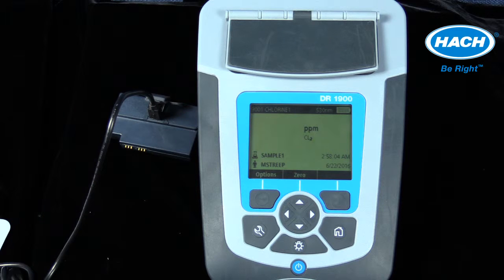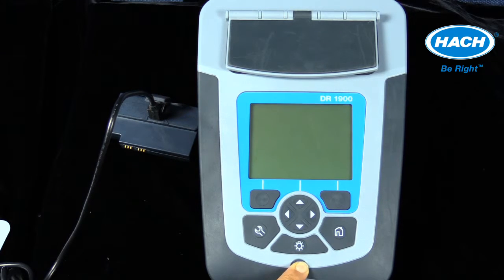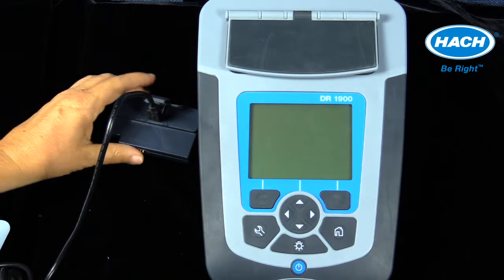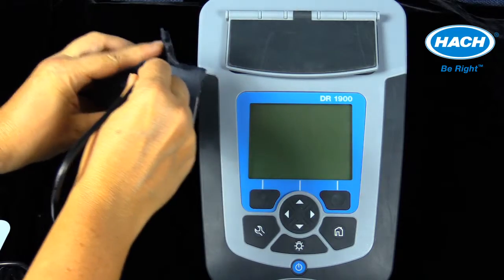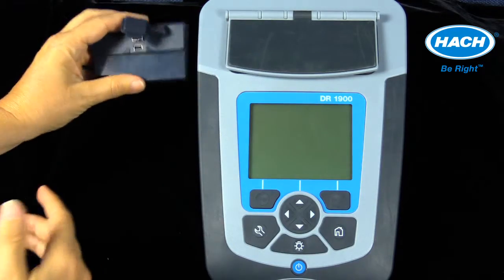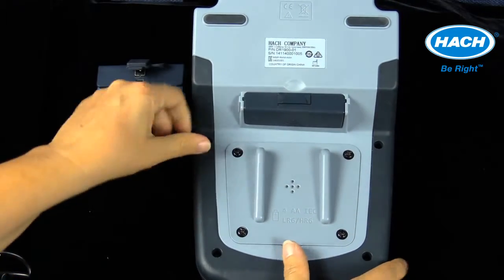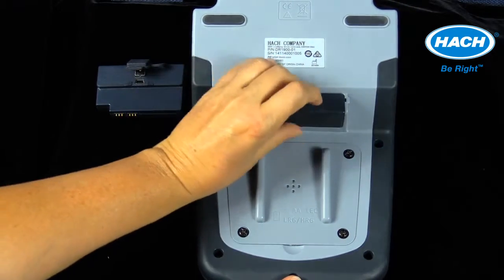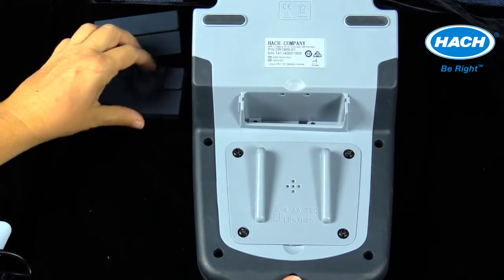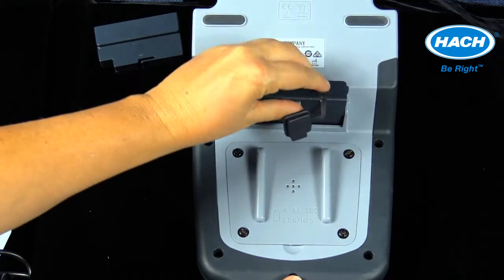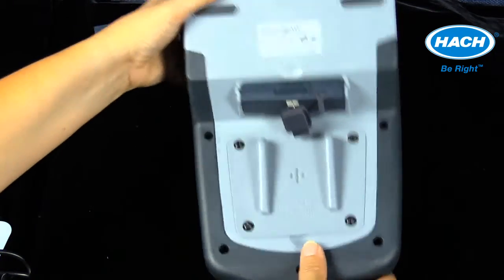The USB module, acting like a USB flash drive, can now be transported to the location of the DR1900 to complete the software update. Power off the DR1900 and remove the module blank by pushing down on the tab and pulling the module straight up from the instrument. To install the USB module, first remove the protective cover from the module and slide into the DR1900 module slot until it clicks into place.